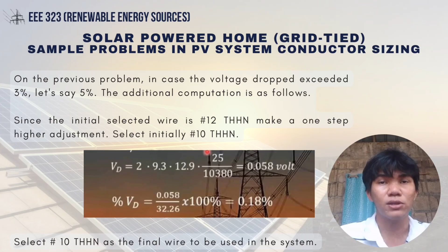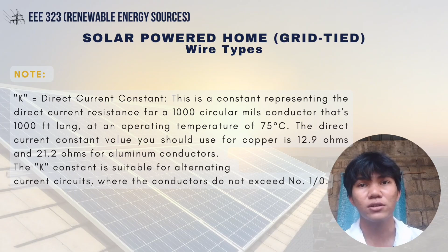Select natin, gagamit tayo ng number 10 THHN wire para sa final wire na gagamitin sa system. Take note, K is equal to the direct current constant, representing the direct current resistance for 1,000 circular mills conductor that's 1000 ft long at an operating temperature of 75 degrees Celsius. The direct current constant value to use is 12.9 for copper and 21.2 ohms for aluminum conductors. The K constant is suitable for alternating current circuits where conductors do not exceed number 1/0.